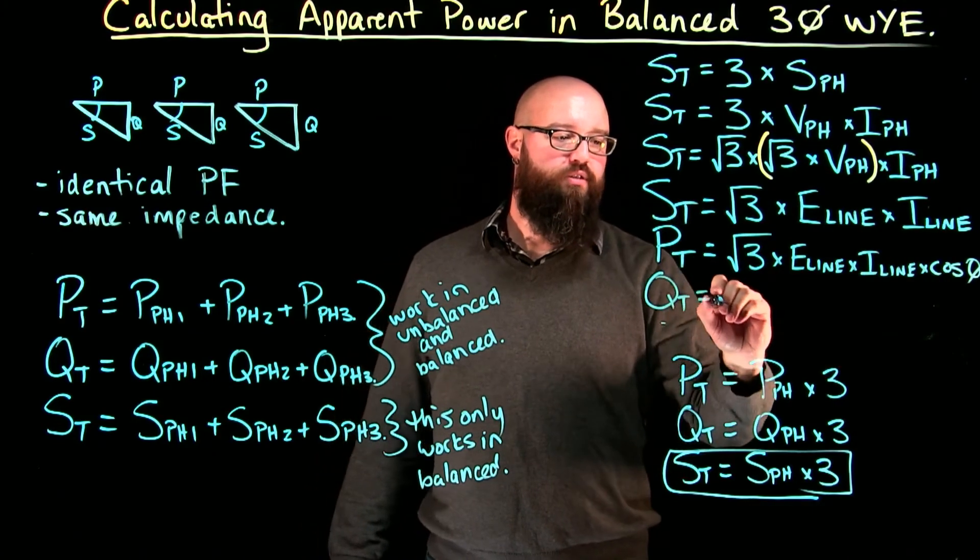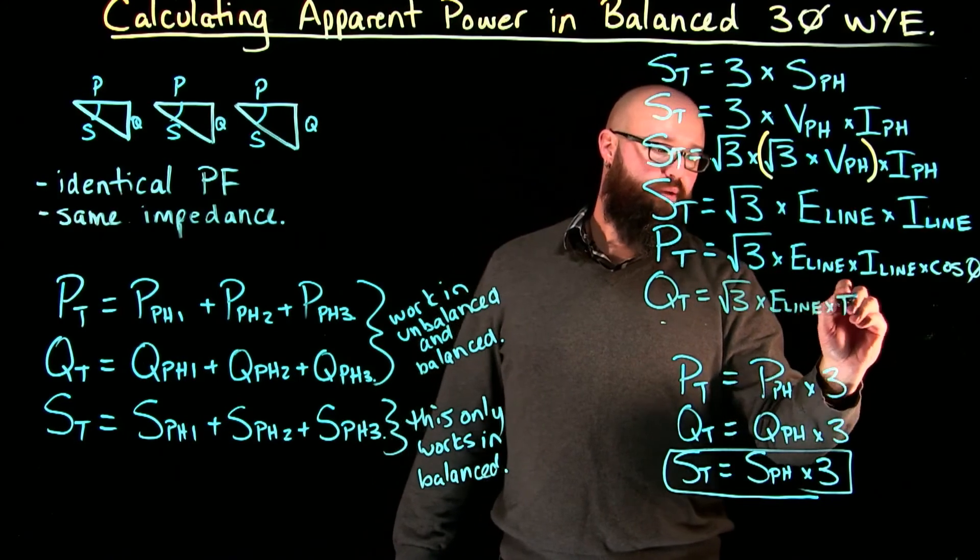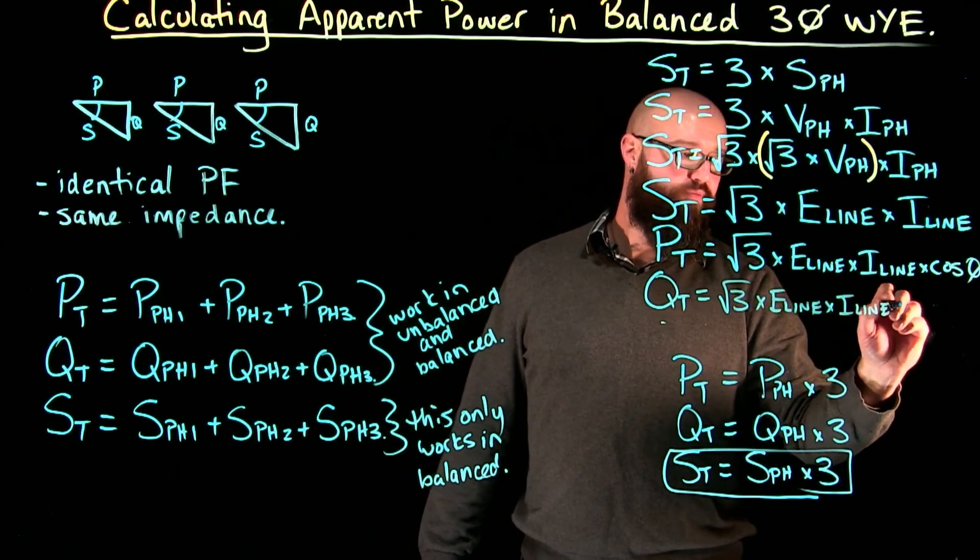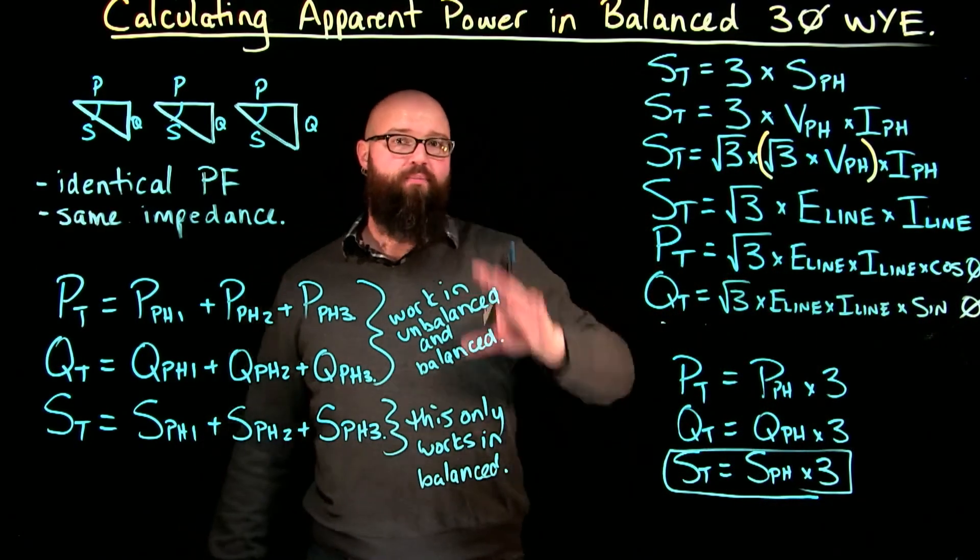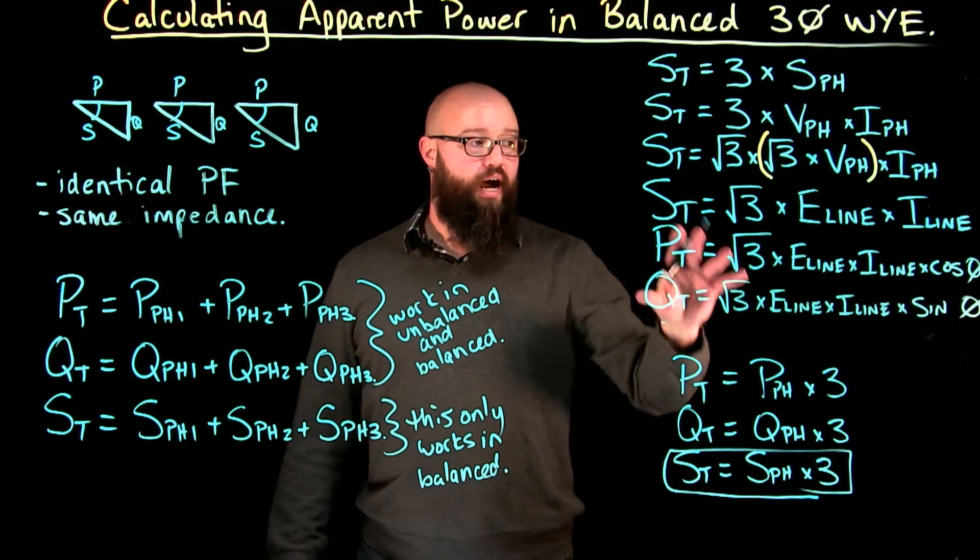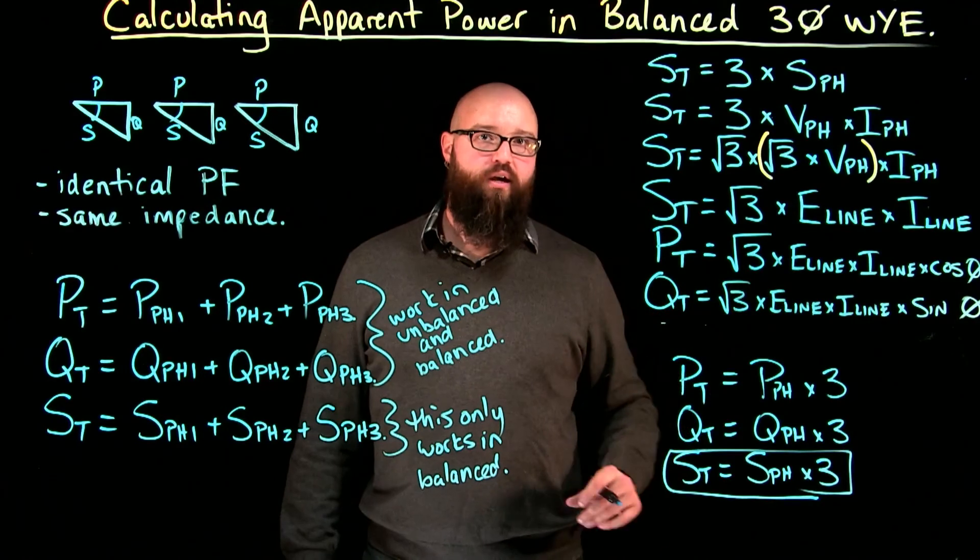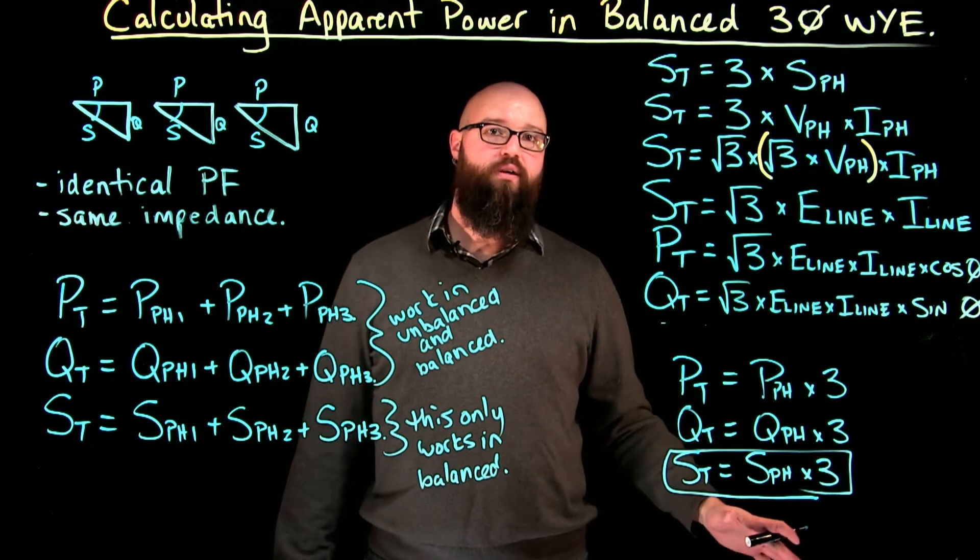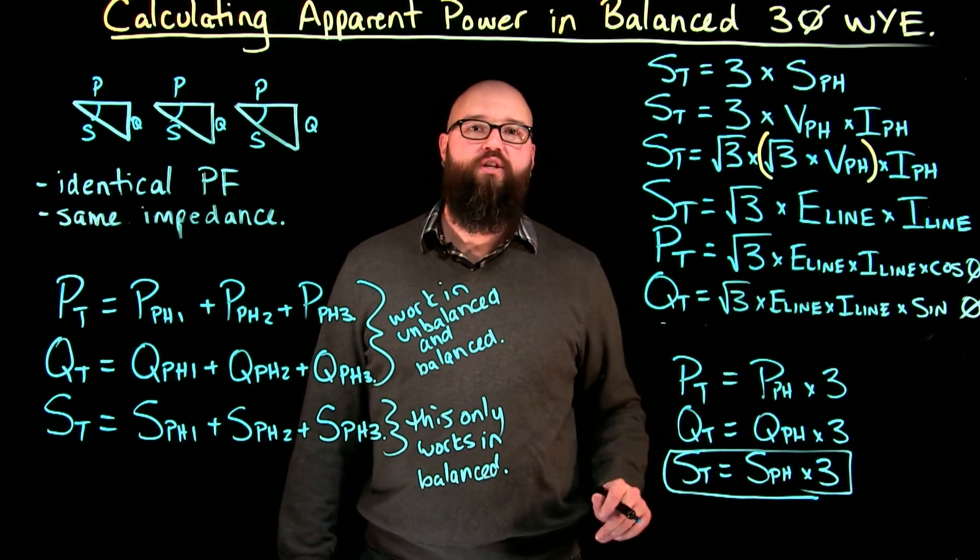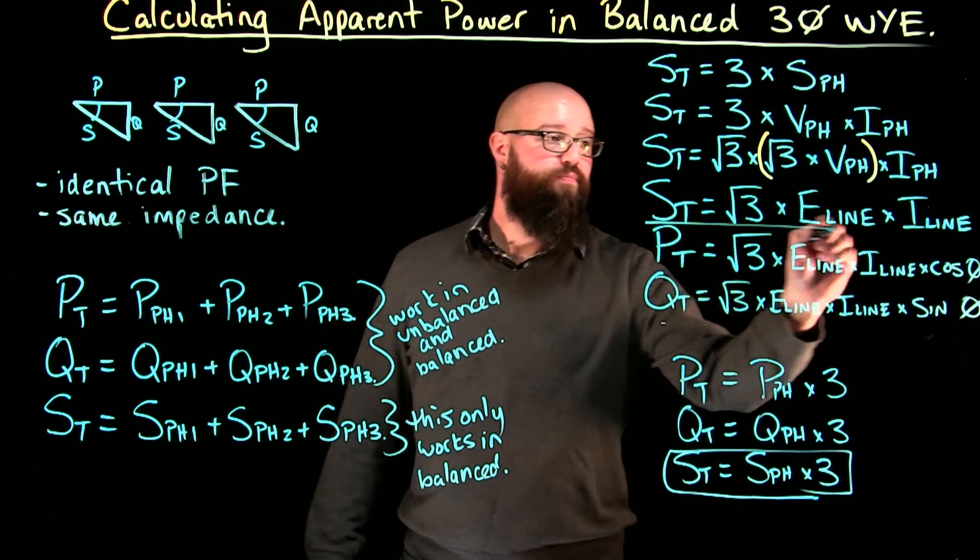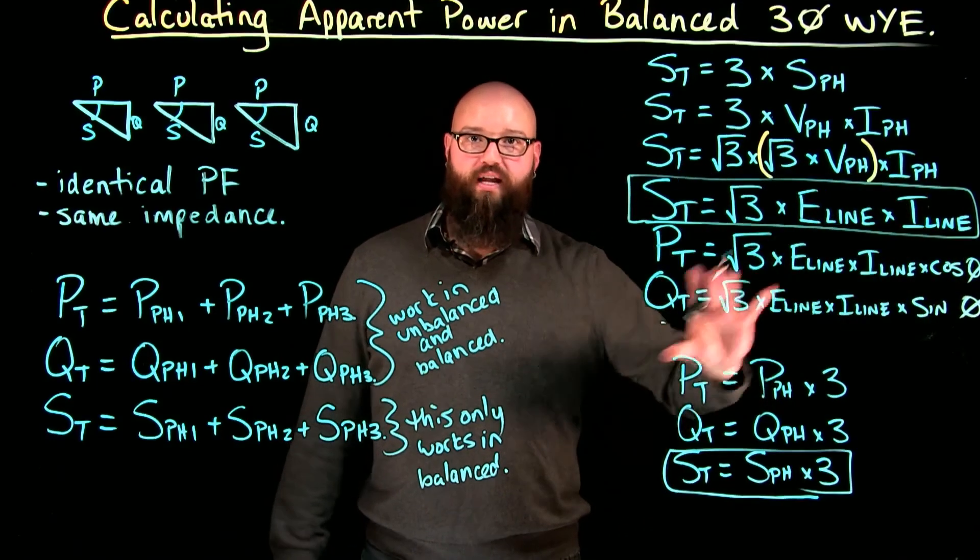Q total equals root three times E line times I line times sin theta. That way, if I'm given an FLA of a motor and say the phase voltage, I can take this and convert it into total apparent power for my circuit. And from there, I can go and find the total power of my circuit, or I could find the total reactive power of my circuit. Or we could work with any combination therein, as long as we can transpose, really, this formula right here. That's going to be our formula for any of these calculations.